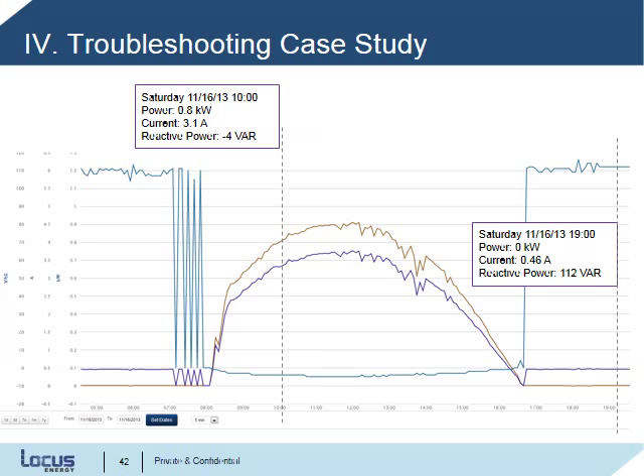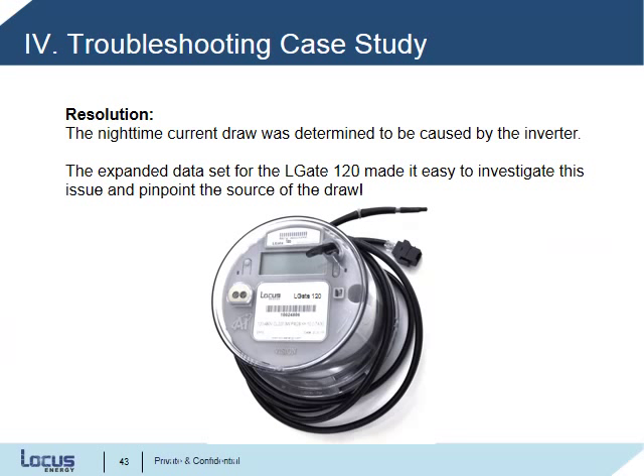We noticed that there was extremely high reactive power at nighttime, upwards of 100 volt amperes. When the inverter was running during the solar day, reactive power stayed within a fairly reasonable range. In the end, we were able to determine that the inverter was drawing significant amperage at night, but close to 0 kW. We learned that this is fairly common behavior for the inverter they had on site, which was an older model. Without the expanded dataset from the LGate 120, we might not have been able to figure this out without a site visit.